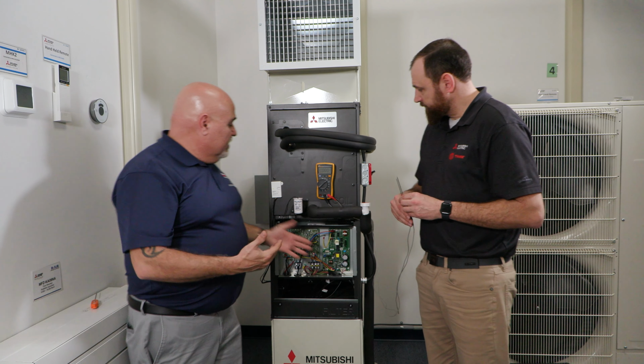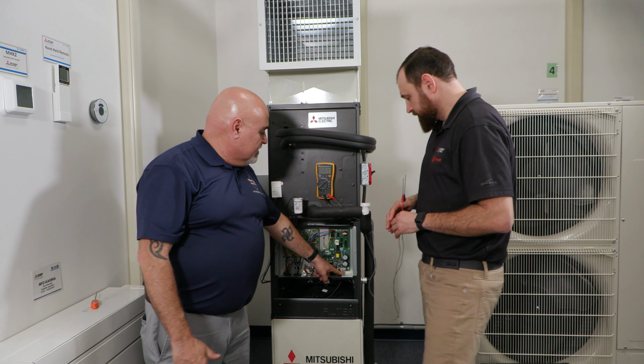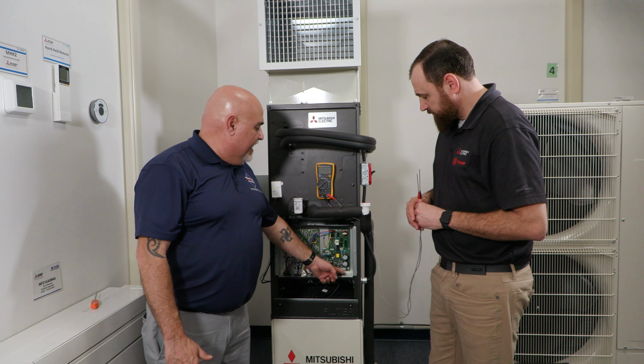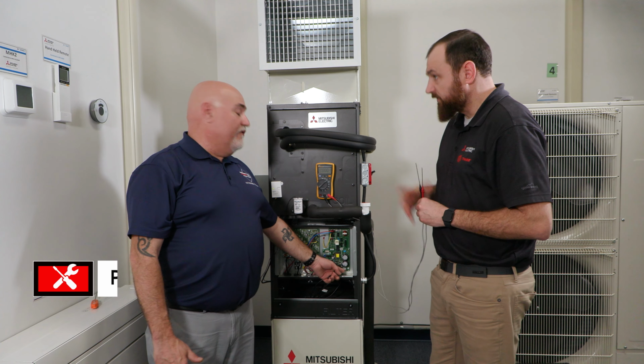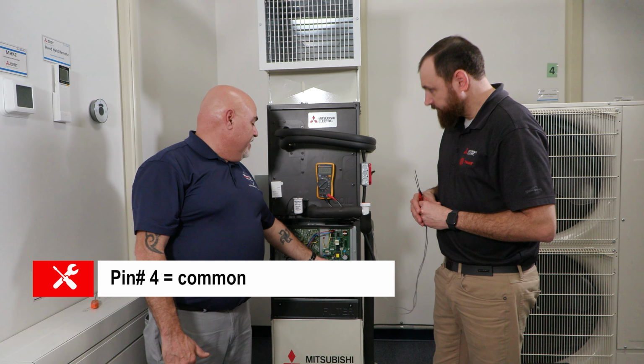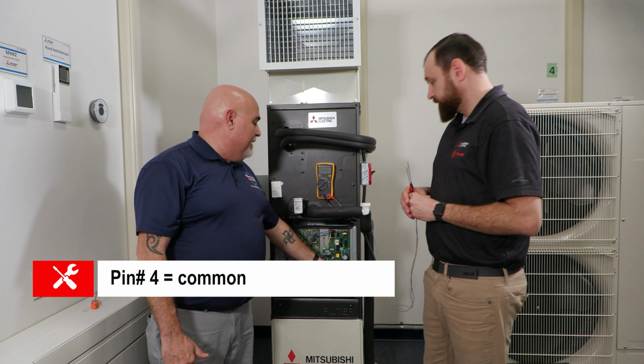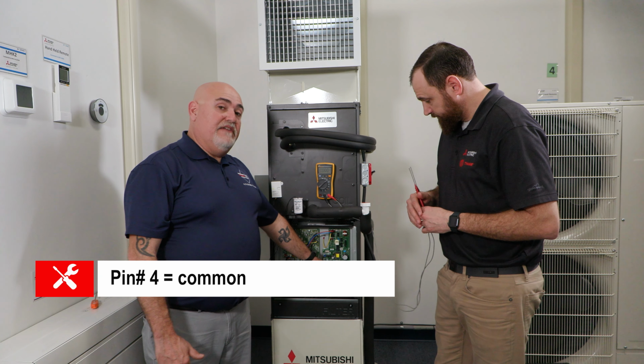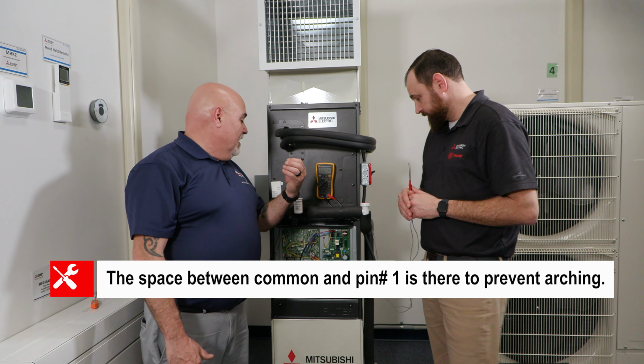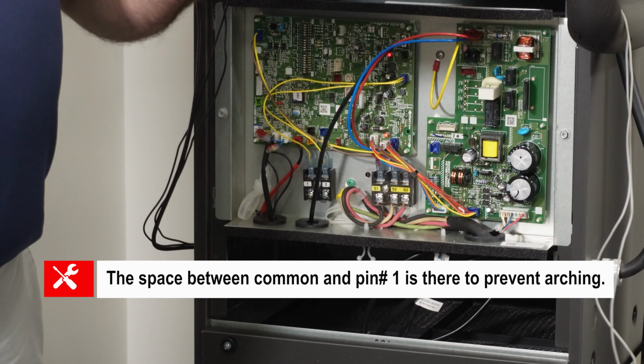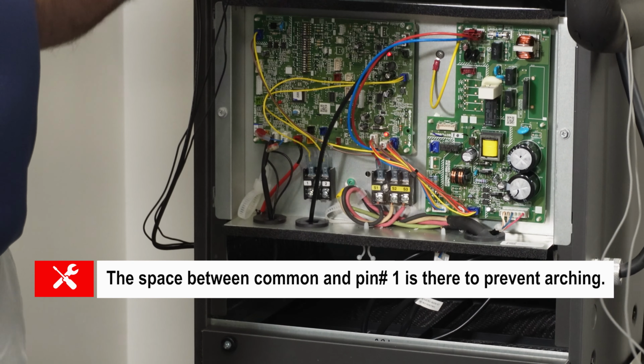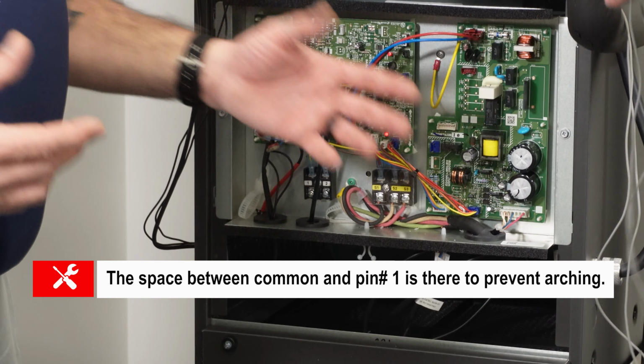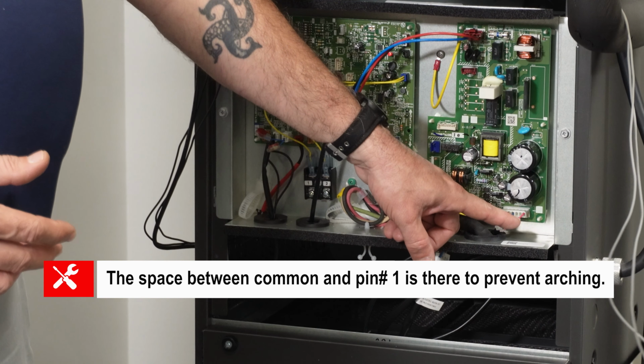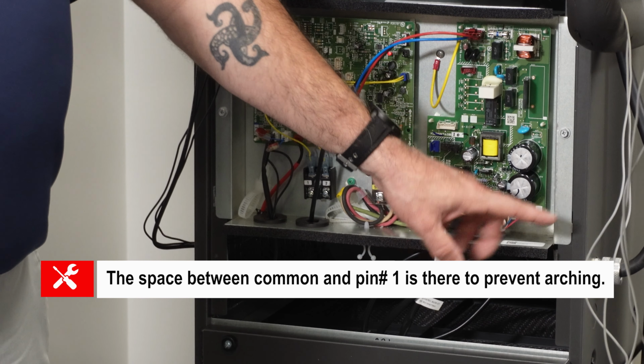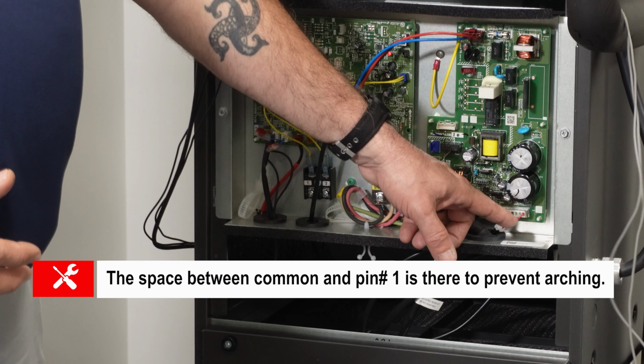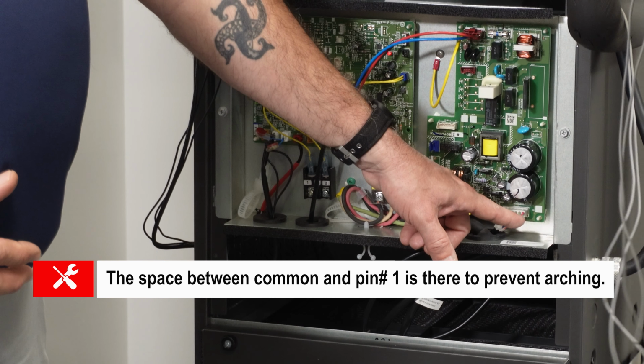Okay. So right now we're going to look at the pins on our connector, and basically we have a common, in this case our blue wire or pin number 4. Between common and pin number 1, we have a space. They purposely leave a space in that connector for prevention of arcing, because we all know that DC voltage likes to jump, it likes to arc. That's our 300 volt feed to the motor, so between common and 1 we should read 300 volts.